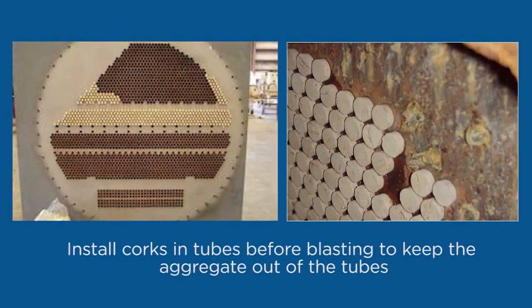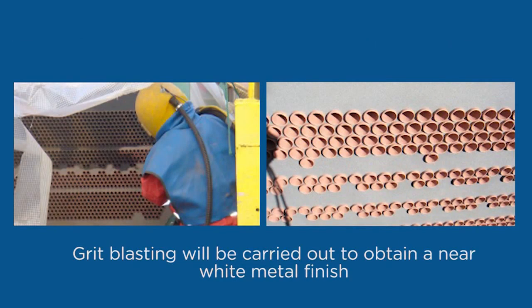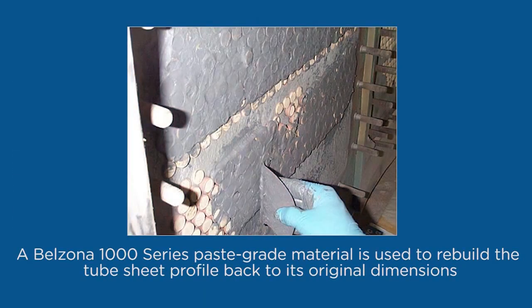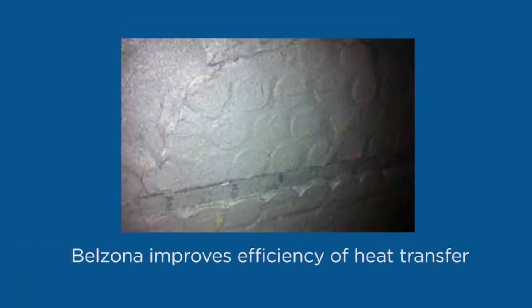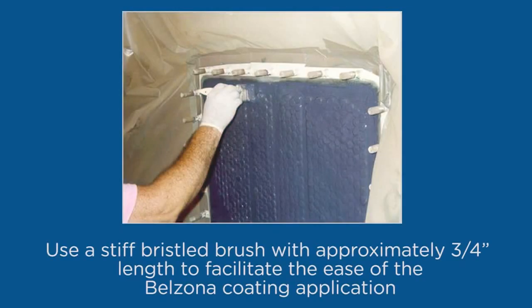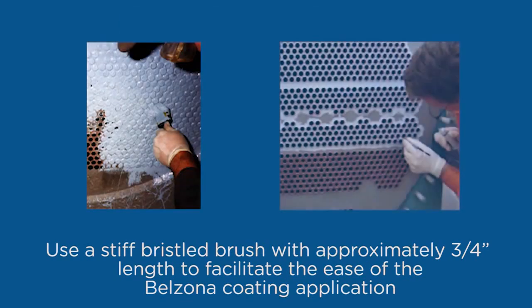The Belzona solution is easy. Once the tubes are dry, corks are inserted before surface preparation to a suitable cleanliness and profile. A paste-grade Belzona metallic polymer is then used to rebuild the tube sheet profile to its original dimensions. The removal of surface irregularities will increase flow characteristics and the efficiency of heat transfer. Using a stiff bristled brush or roller, the Belzona protective coating is applied to the sheet, while ensuring that the tube's profile can be seen through the coating thickness.